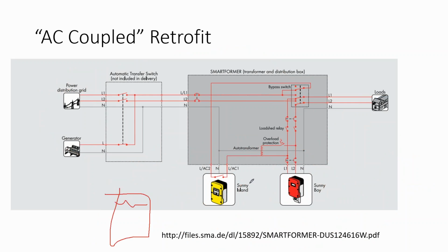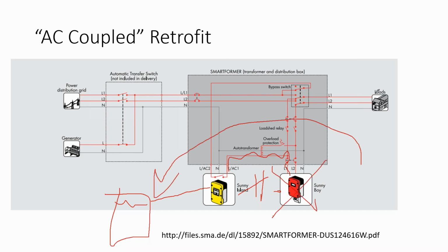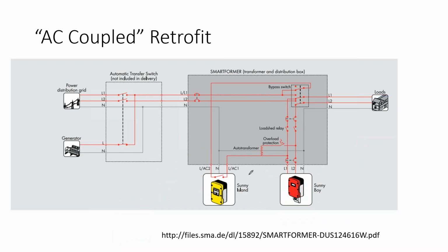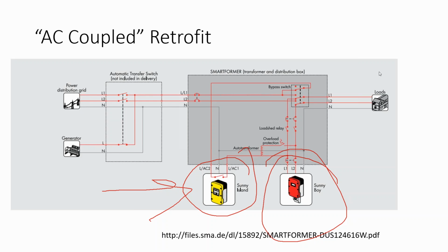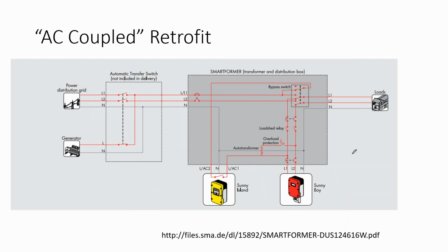anti-islanding detection. So there are control circuits in your solar inverters so that the instant there's a blip in the electric grid, it turns off. And so your battery inverter will use that same protection that's part of a UL listing in order to trick the solar inverter into turning off. And so when you have a battery inverter that is different than your solar inverter, they can still use this kind of trick in order to turn the array off so that you're not overcharging your batteries. Now that's for a grid connected battery inverter and a grid connected solar inverter. If you go and use an off-grid battery inverter, it may not have the same controls inside it.